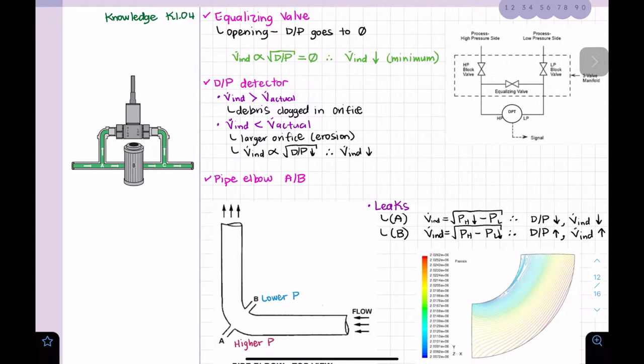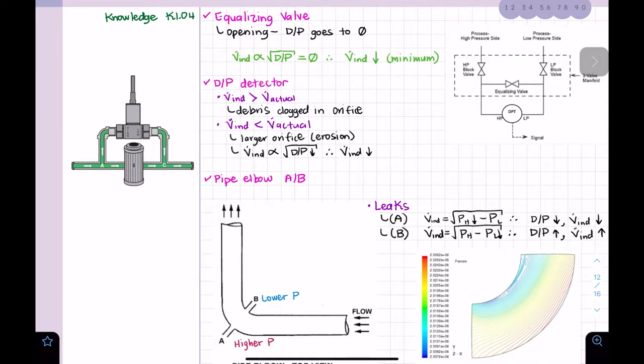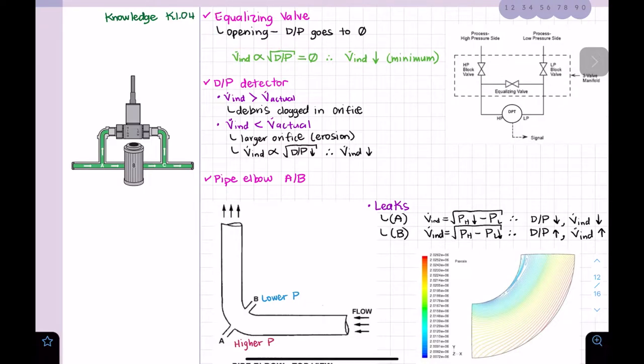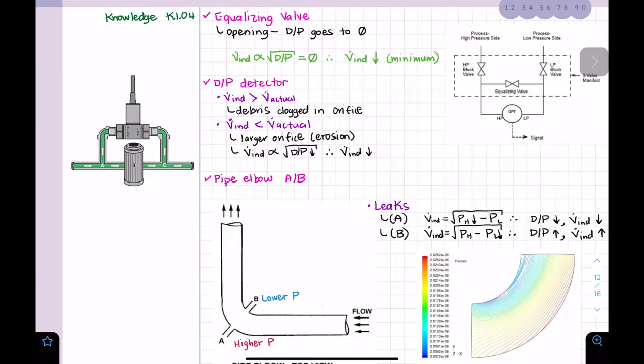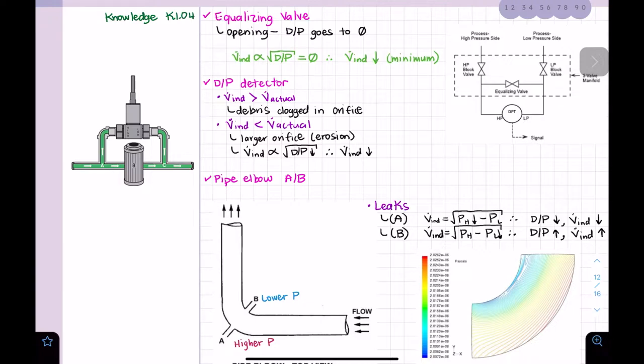The pressure does not equalize to zero — the equalized pressure is the same on both the high and low sides. At that point, whatever steps are necessary to adjust — like zeroing a transmitter — can be done. For GFES purposes, when we open the equalizing valve, the differential pressure goes to zero, so our flow indication, which is proportional to the square root of the differential pressure, will drop to a minimum.